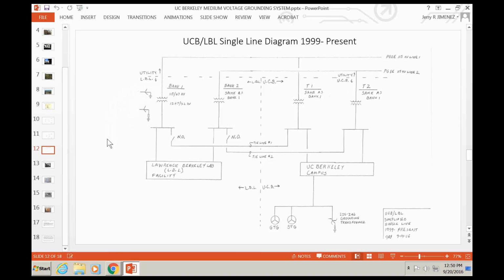Do you know why the decision was made to go with low resistance grounding as opposed to high resistance? Is this Keith? Yeah, Keith, I covered that, but maybe you weren't here. There were lots of collaborative discussions between the Lawrence Berkeley Lab people and the University of California people here, and one party wanted to limit the ground fault current to 1,000 amps, and the other party wanted to limit it to 3,000 amps. I heard that high resistance grounding would limit it to something like 30 amps. Oh, yeah, I think you might get into a little trouble with voltage excursions if you put high resistance grounding on the 12 kV system.